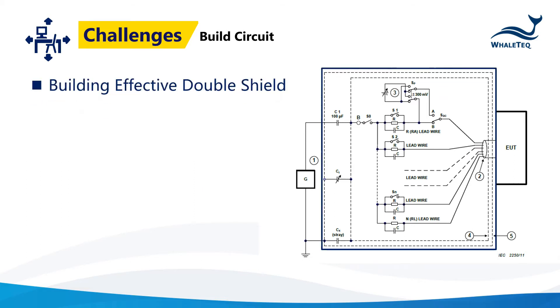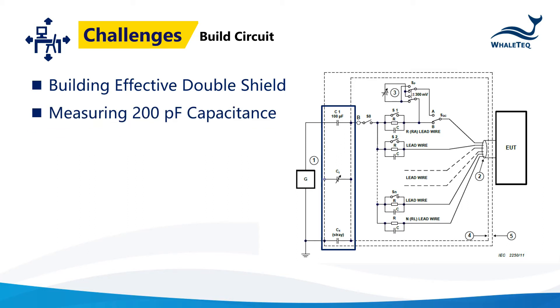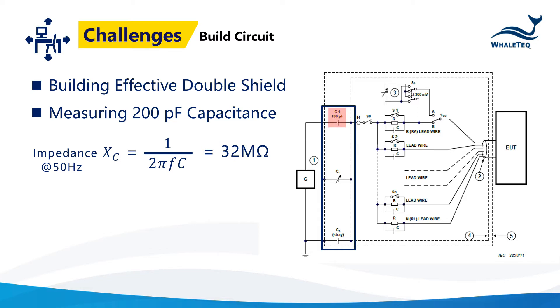Challenge 1: Because the test setup is very sensitive to external noise, a double shield is required by the standard. Setting up an effective double shield to control noise is critical to running consistent tests. Challenge 2: The standard also requires you to set up 200 pF equivalent capacitors to simulate the capacitance from the human body. But due to the high impedance of the 100 pF divider, measuring and adjusting the stray capacitor here is very difficult.